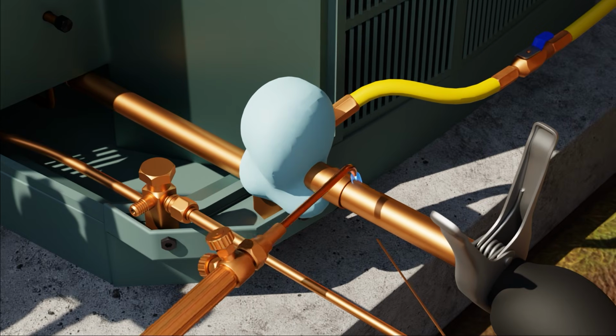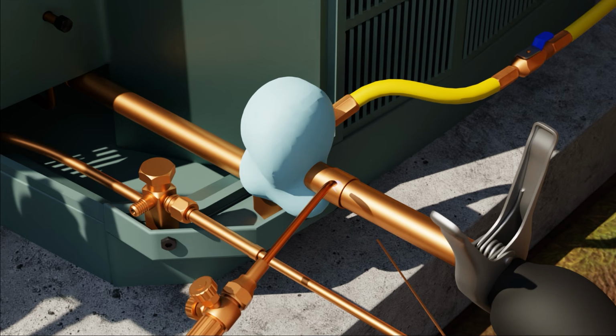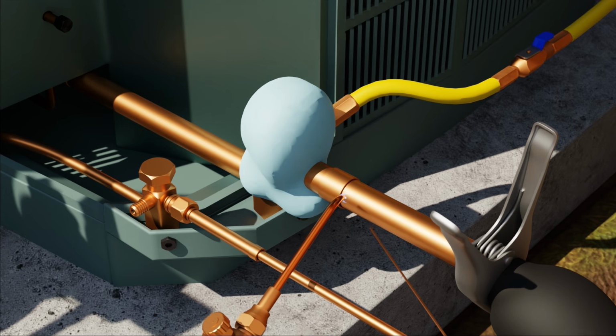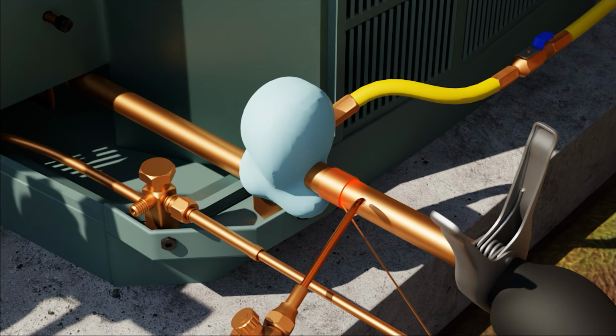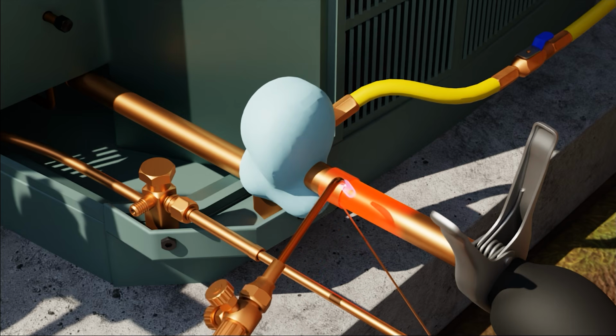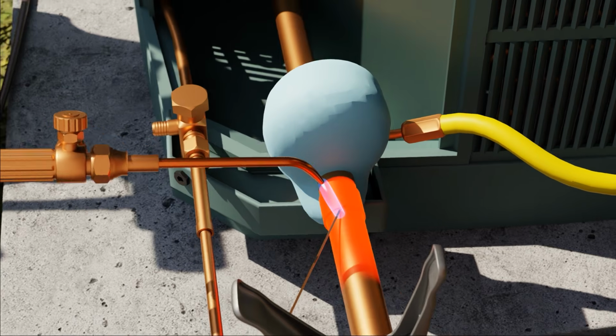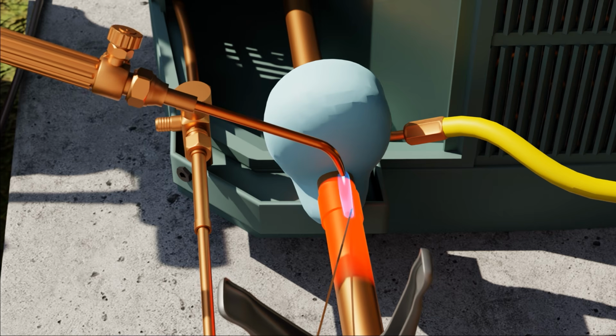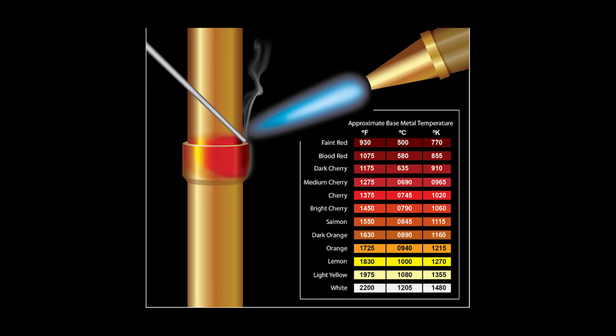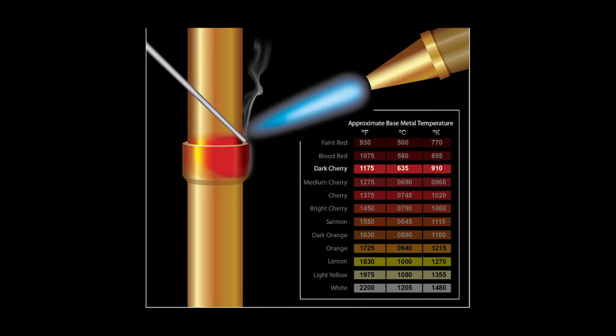Now we're going to heat the connection by starting on the male end, getting it nice and hot to that dark cherry red, and conducting that heat into the joint connection. The color we're showing here is about the color you want it to get. It's hard to represent this on a computer screen and there will be some variation, but that color is called deep cherry red or dark cherry red. That means our base copper is around 1200 degrees, which is also the melting temperature of most brazing alloy rods.